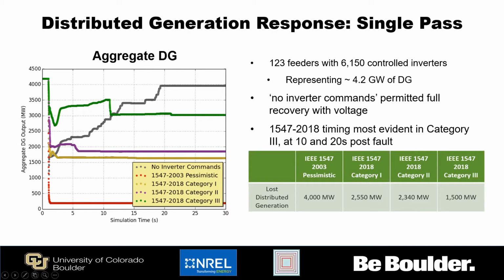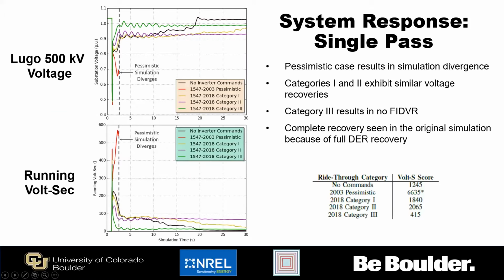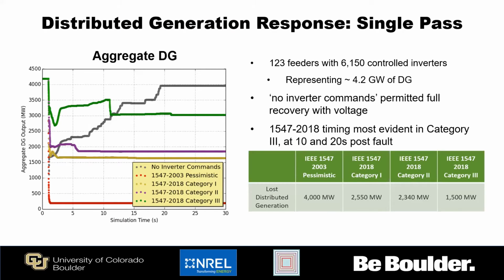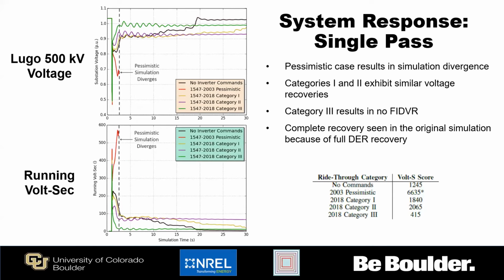You can see varying responses based on the other IEEE 1547 standards. Category 1, for example, has a larger amount dropped. Category 2 is slightly better. And then category 3 retains roughly 80% of the generation or so. This is over 123 different feeders with over 6,000 different individual inverters explicitly, so that's about 4.2 gigawatts of DG. You can see from the numbers below how much is lost. It ranges from 4,000 megawatts to, for the 1547-2018 category 3, only 1,500 megawatts lost.